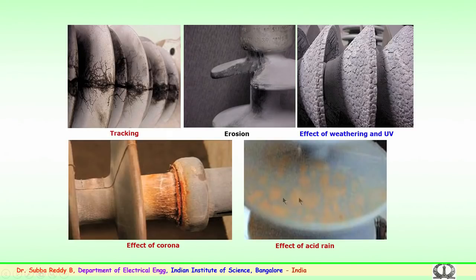It could be tracking; you can see here the tracking of the insulator over a period of time. This could be because of continuous surface degradation, where the electric arc or the current starts conducting and a flashover happens over the surface. This leads to the failure of the entire string, and replacement is needed. The second is erosion. You can see the material peeling off over a period of time.